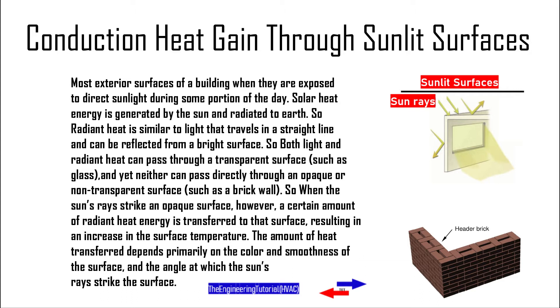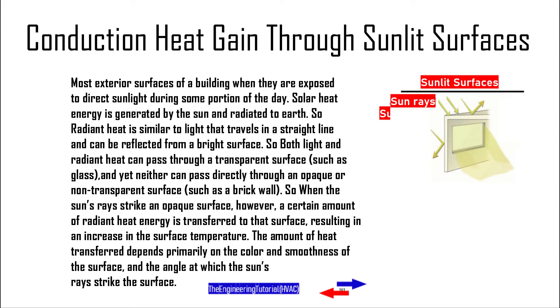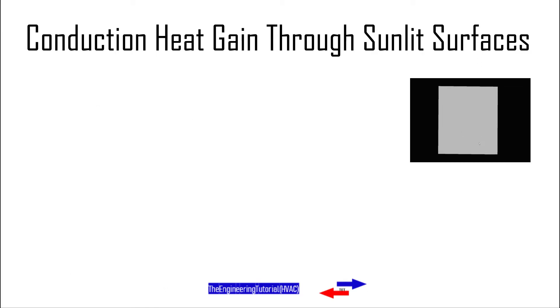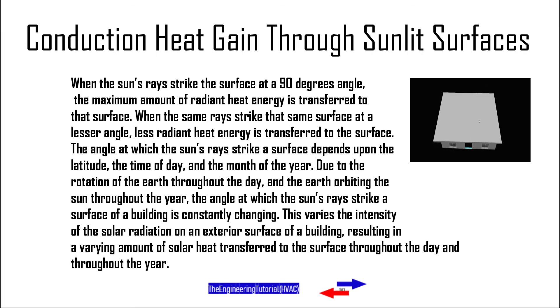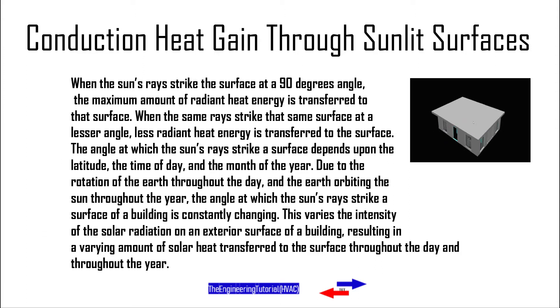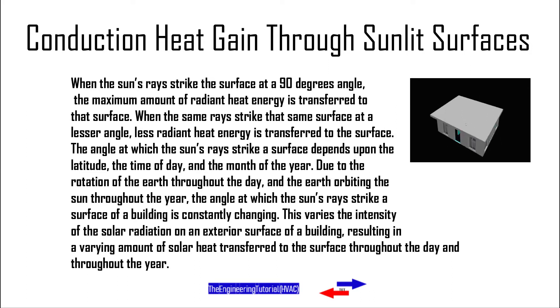When the sun's rays strike an opaque surface, a certain amount of radiant heat energy is transferred to that surface, resulting in an increase in the surface temperature. The amount of heat transfer depends primarily on the color and smoothness of the surface, and the angle at which the sun's rays strike the surface. When the sun's rays strike the surface at a 90-degree angle, the maximum amount of radiant heat energy is transferred. When the same rays strike that surface at a lesser angle, less radiant heat energy is transferred.